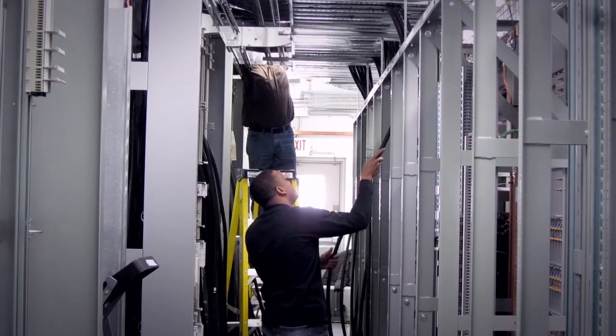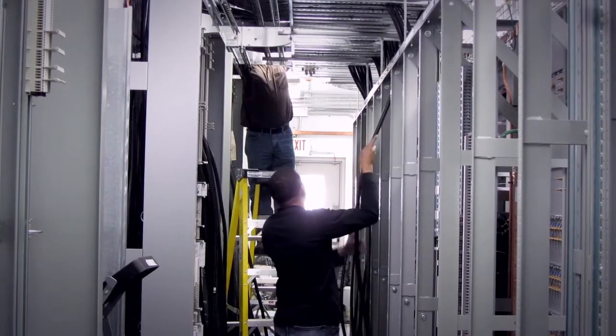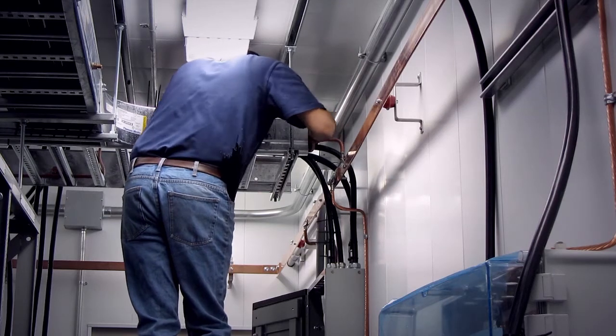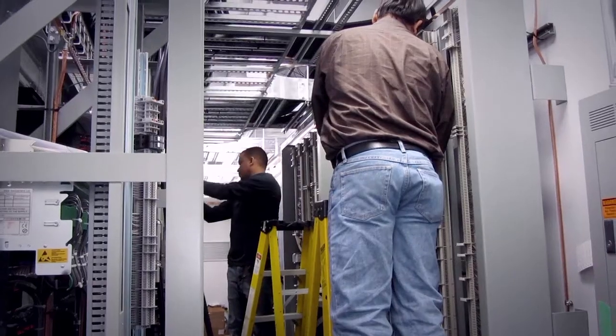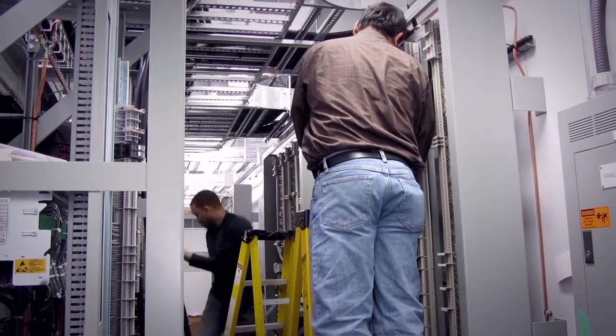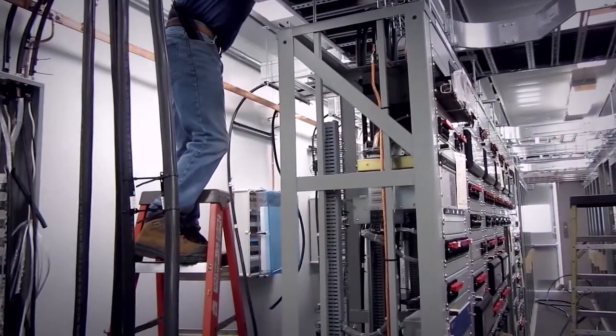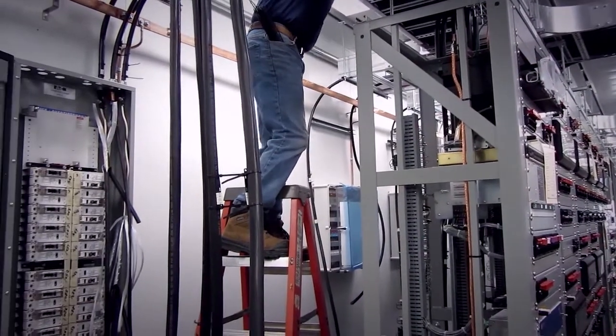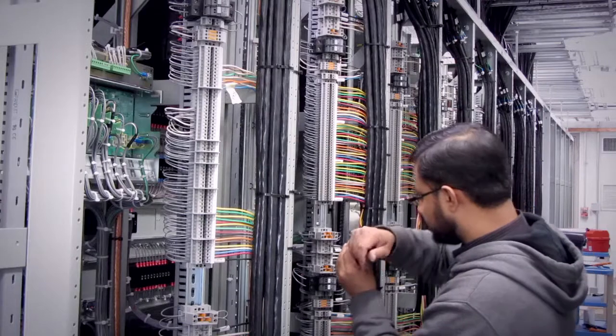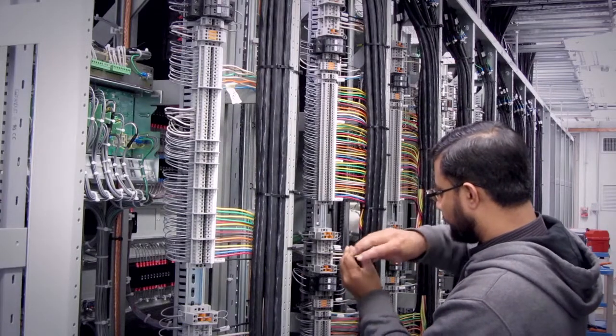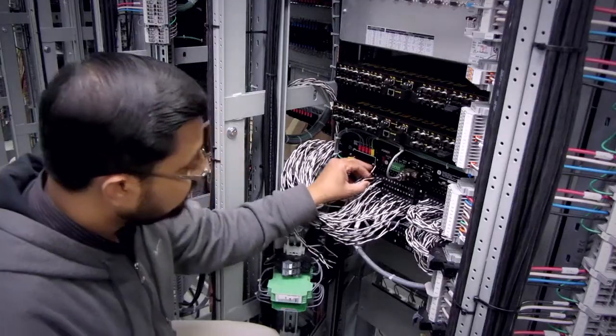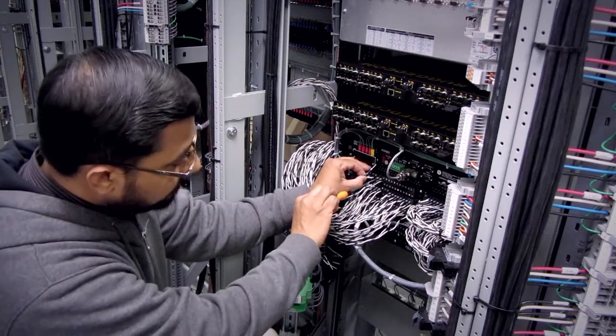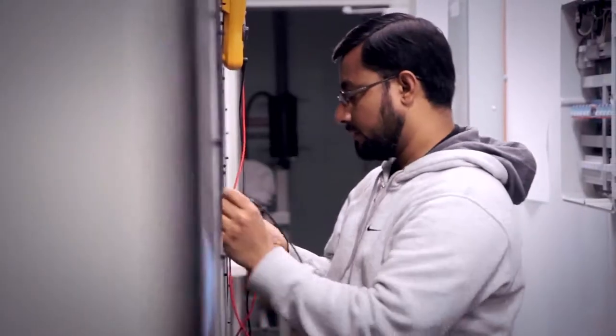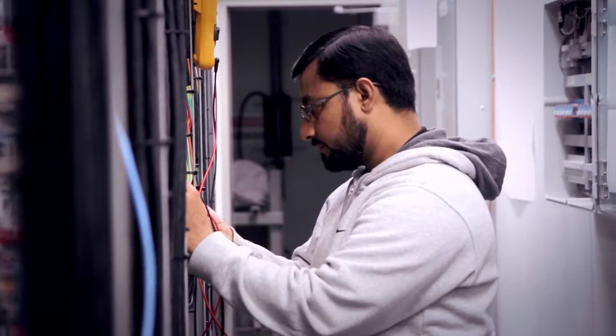Cabling and interconnection of all the components in the building is the next step. Cabling interconnection drawings are again issued for construction to the cabling electricians. This work involves installing multi-conductor cables in special cable trays installed above the panels. Cables are labeled and then individual cable pairs are terminated on the device and panel terminal blocks within the various panels. Again, as with all electrical wiring connections made, testing has to take place.